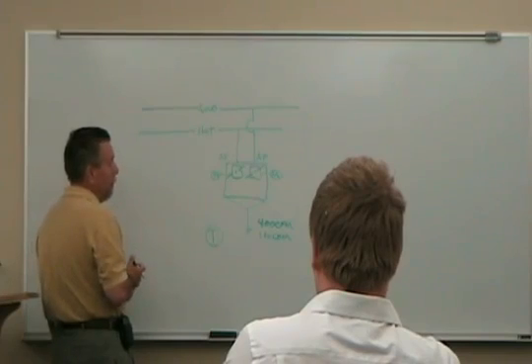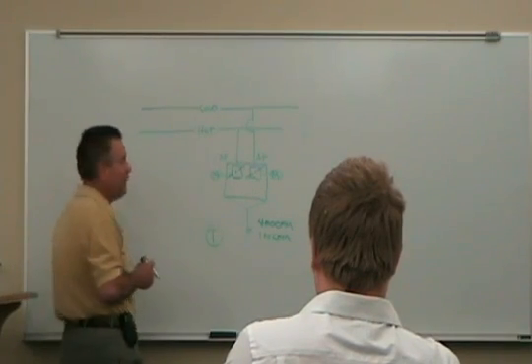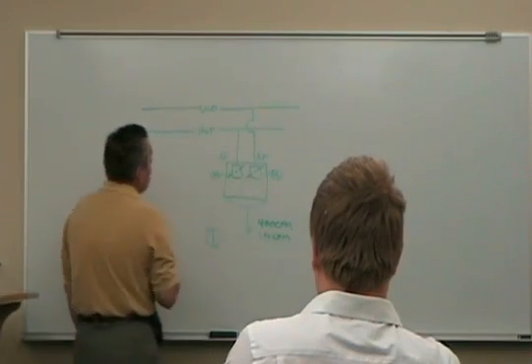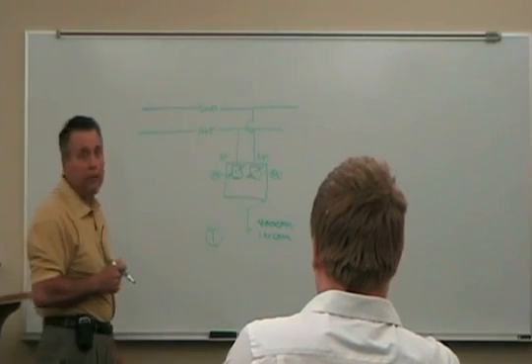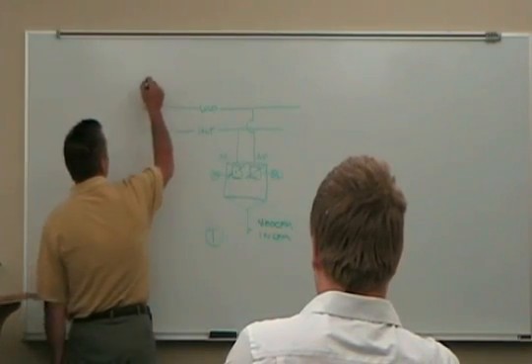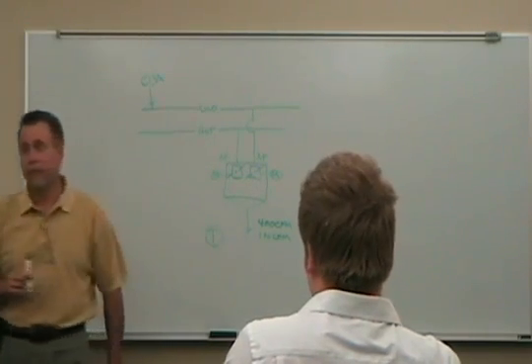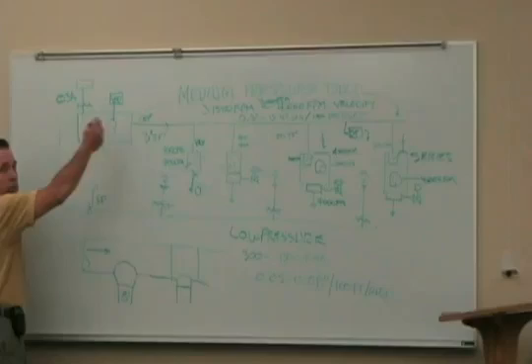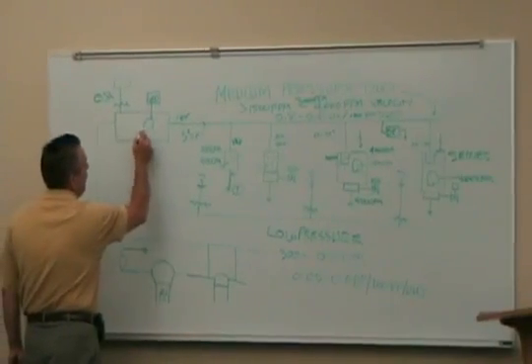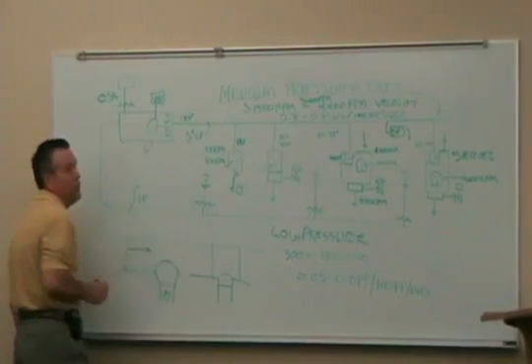There's a little programming problem right there. Which one do I use for minimum CFM? Generally, and this is open to the type of design, generally the outside air is connected to the cold duct. Because in this air handling unit, the way it's constructed, remember I had kind of a twin airstream. One was hot, one was cold. I had cooling coils and heating coils.